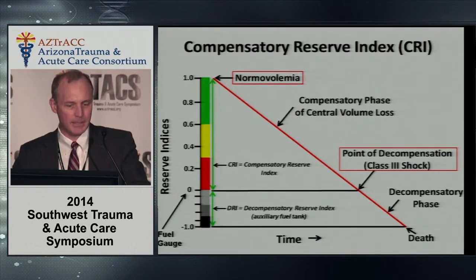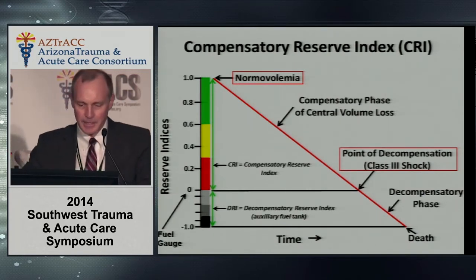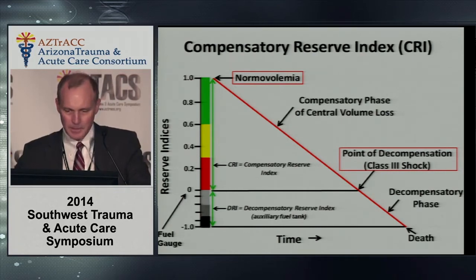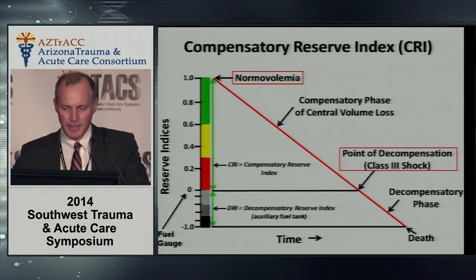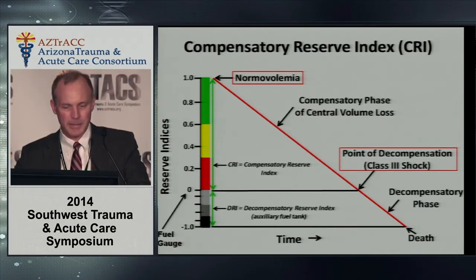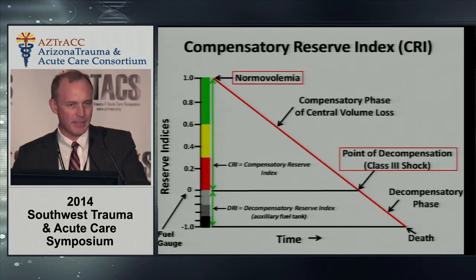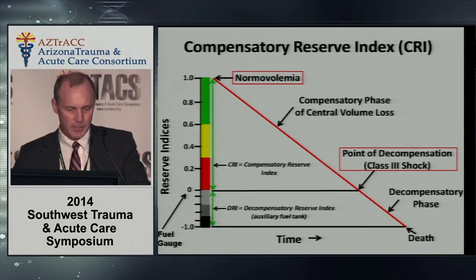The compensatory phase of central volume loss extends from normovolemia to decompensation or class III shock. The algorithm calculates an individual-specific beat-to-beat composite measure of compensation by monitoring a select group of waveform features that trend the compensatory phase of central volume loss. We call this algorithm the Compensatory Reserve Index, or CRI. We like to think of CRI as a fuel gauge, where a CRI of 1 indicates replete central volume — a full tank — and a CRI of 0 indicates the tank is empty, reaching the point of decompensation. Values between 1 and 0 indicate the compensatory reserve of the individual.